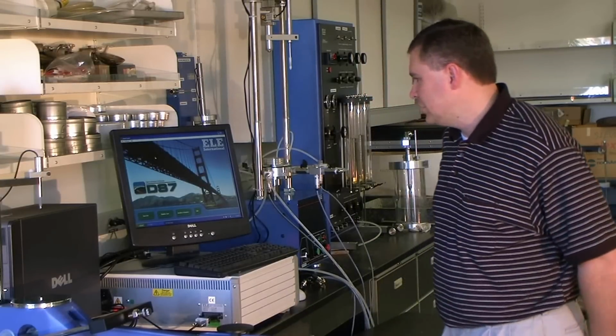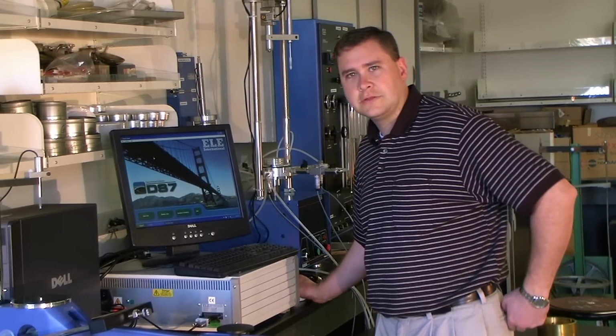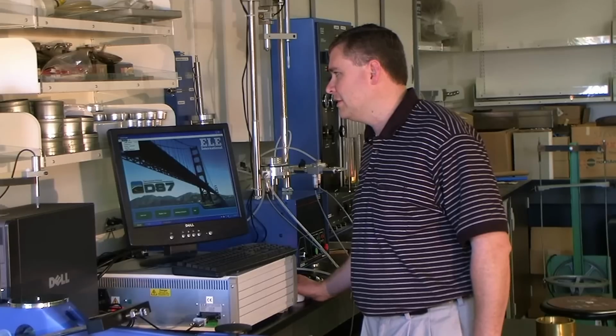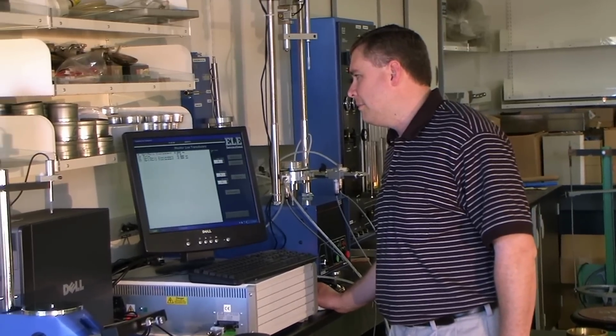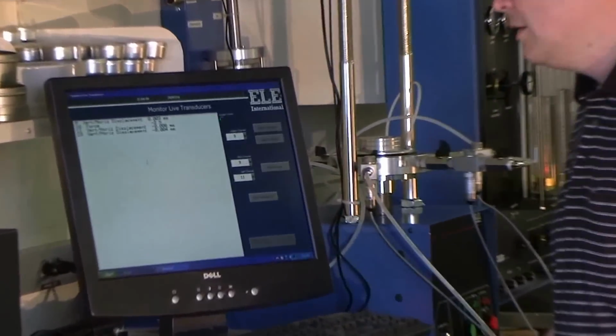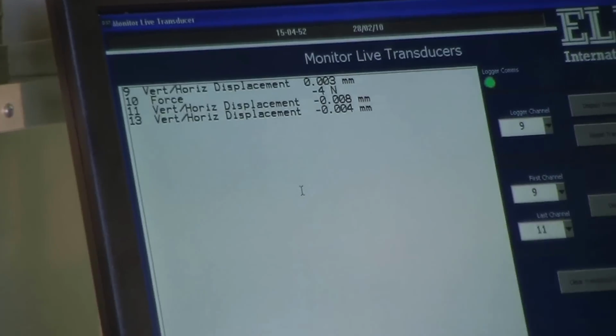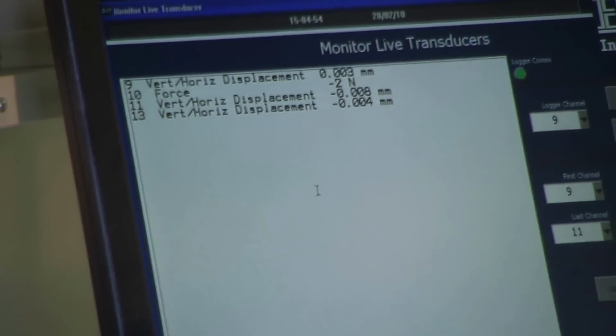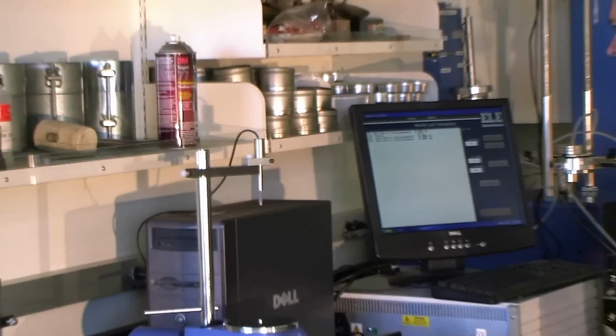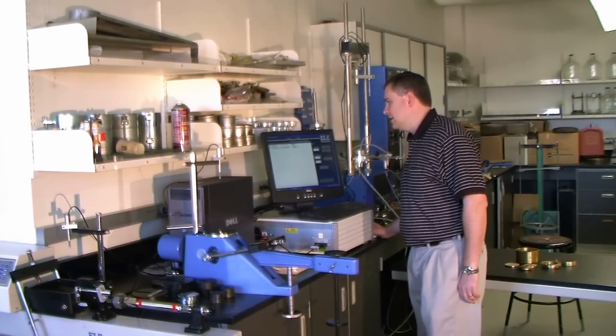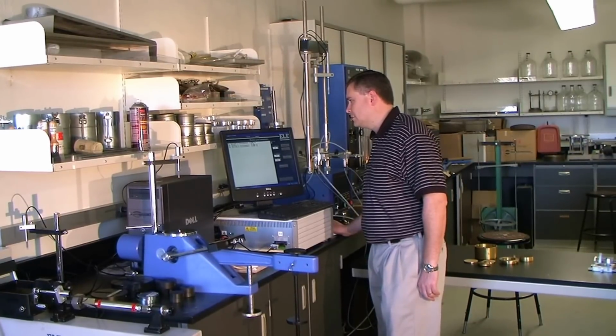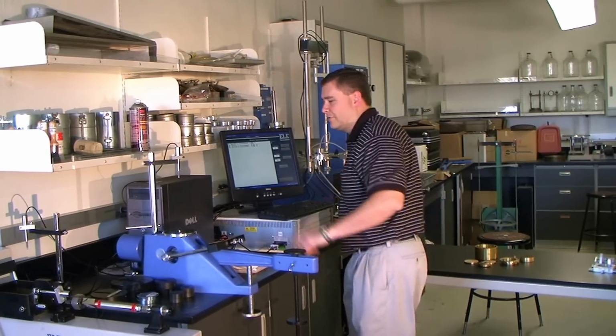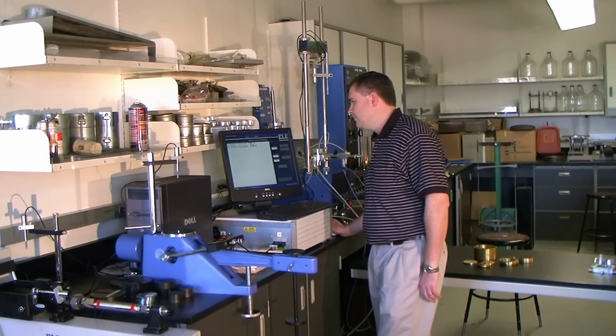Alright, now we'll check the transducer calibration to make sure that they're reading the appropriate way. Go to Monitor Transducer. We've entered in the calibration data for all 4 of these. These are the 3 for the direct shear machine and the 1 for the consolidation apparatus. Channel 9, 10, 11 are the horizontal force and vertical displacement transducers for the direct shear machine.